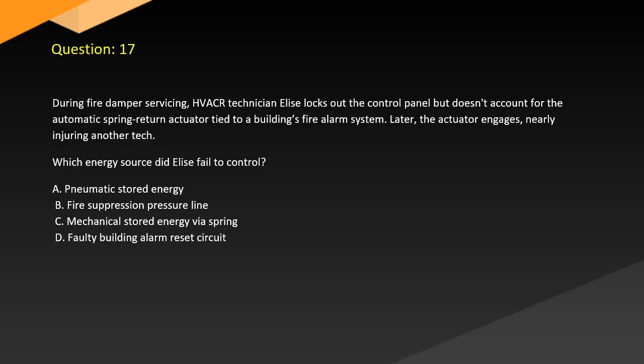Question 17. During fire damper servicing, an HVACR technician locks out the control panel but doesn't account for the automatic spring return actuator tied to a building's fire alarm system. Later, the actuator engages, nearly injuring another tech. Which energy source did Elise fail to control? A. The pneumatic stored energy. B. Fire suppression pressure line. C. Mechanical stored energy via spring. D. Faulty building alarm reset circuit.